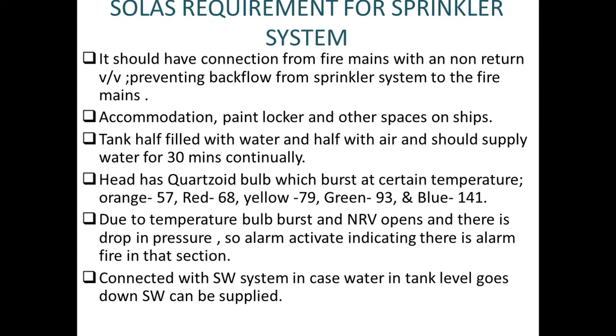It should have a connection from the fire mains with a non-return valve. Whenever we are talking about the seawater system, we have to have a connection from the fire main system, preventing backflow, with a non-return valve arrangement. Why are we keeping that focus on the non-return valve arrangement? Because we need to prevent backflow from the sprinkler system to the fire main. The water cannot go from the sprinkler system to the fire main system.